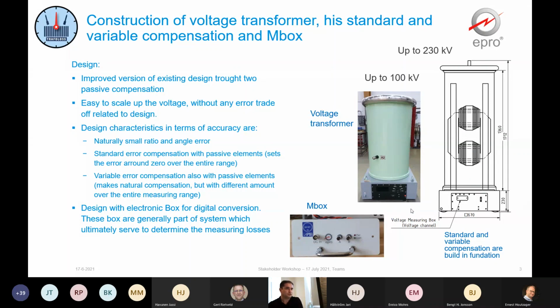When we talk about the three-phase system, every voltage and current transformer has its own M-box. From there we have our digital wattmeter. Anyway, for this project we were looking more closely at the one voltage channel and trying to validate it as best as possible. Also, the M-boxes have the possibility to compensate some error if it's necessary. You can make tiny corrections on many points over the entire measuring range, both for value and for the angle.